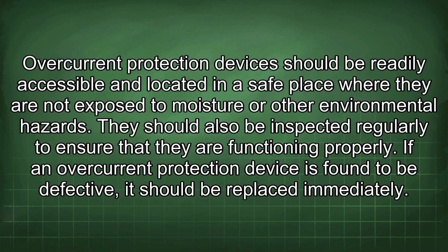Overcurrent protection devices should be readily accessible and located in a safe place where they are not exposed to moisture or other environmental hazards. They should also be inspected regularly to ensure that they are functioning properly. If an overcurrent protection device is found to be defective, it should be replaced immediately.